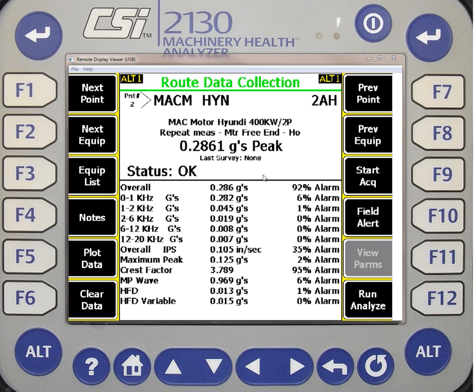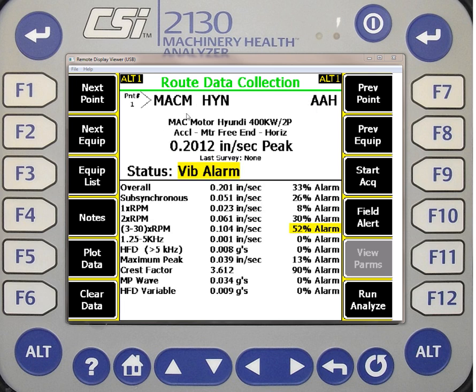I've got one other data point in here that I just want to bring up briefly, and in this case I've got all that same information, but this time the vibration level was a little bit too big and it triggered an alarm. Now it turns out that this is a very mild alarm. It's a rate of change type of alarm, so it's a very early warning type signal that something's starting to change and might be a problem, in this case within the next year, if it keeps increasing at the current rate. So it's a very powerful tool.